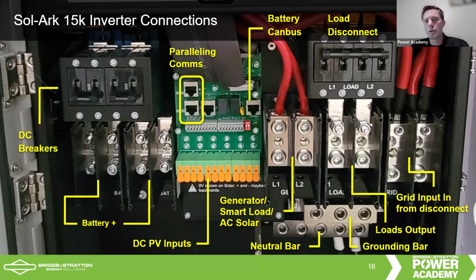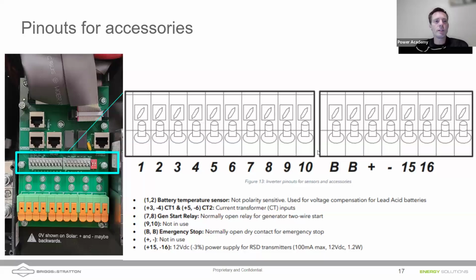And then your output, your 200 amp output. This is not a breaker, just a disconnect here, and this will disconnect your load center if you do need to shut the loads off in the house. We've got our grounding bar here and our neutral bar on the bottom. So wiring is quite reasonable in this inverter, especially when compared to the competition. There's plenty of room inside that wiring bay. Neutral bar might be a little hard, but the wiring is generally pretty simple on a 15K. Got a lot of room to work with.